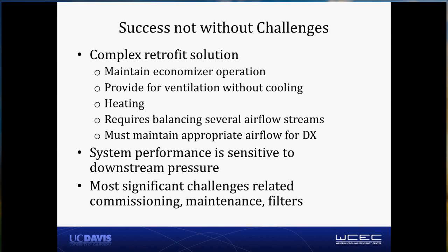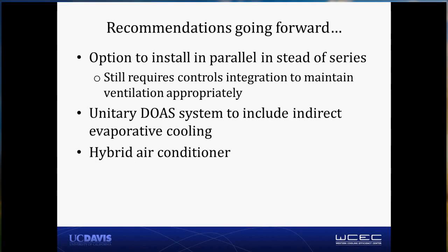And then the most significant challenges were really related to commissioning and maintenance. For example, because these units are bringing in 100% outside air, and applied in Bakersfield, in fact, which has terrible outside air quality, the filters loaded very quickly. In hindsight, we think that they need to be replaced about every 30 days, which is consistent with recommendations from the manufacturers, both these manufacturers and others. But it was sort of difficult to get that done correctly, you could say. Also, we experienced some freeze damage during the period of time this winter when we dropped well below freezing for a few days, and that really shouldn't have happened if the equipment was being maintained and shut down appropriately during the wintertime months. But the folks that were supposed to be doing that didn't manage to do it. So those are some challenges going forward.